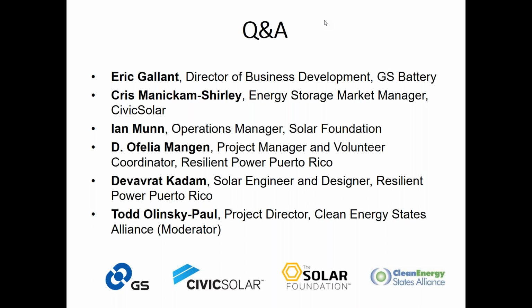Regarding storage systems, the battery we most commonly deploy to the Caribbean for microgrids and nanogrids, and for use with PV, carries a 10-year warranty and is designed for 5,000 cycles at 70% depth of discharge. We're currently testing this battery to a standard called IEC 61427, which simulates conditions in a typical PV environment, taking into account seasonal variability, partial state of charge, and other factors. In that test, each cycle is equivalent to one year of service.